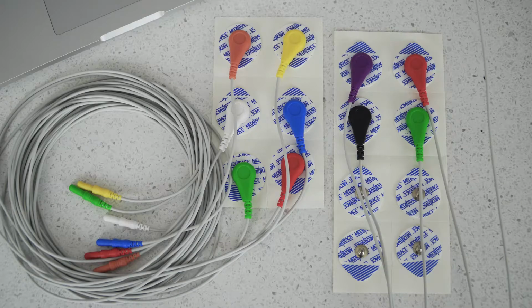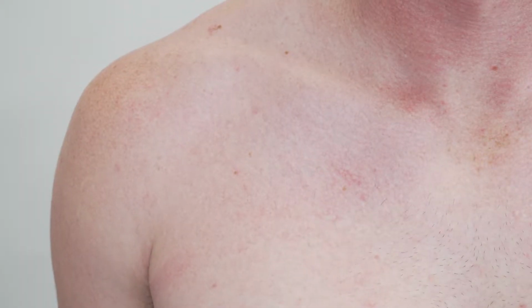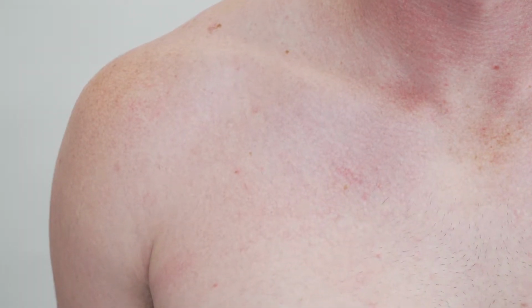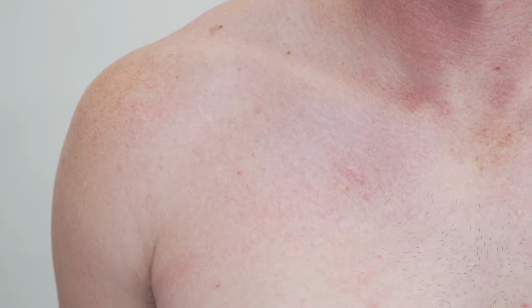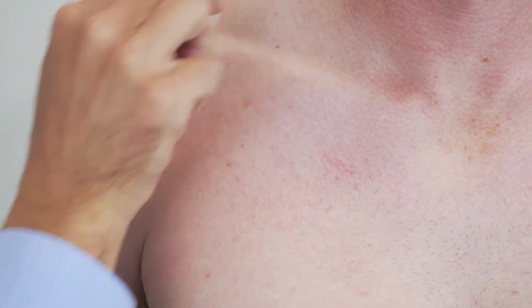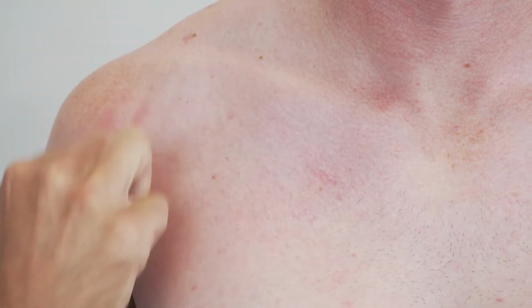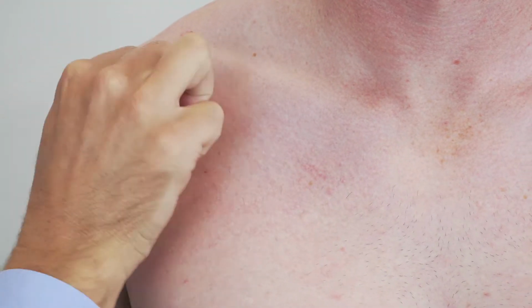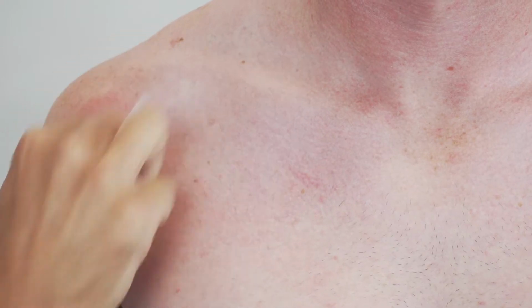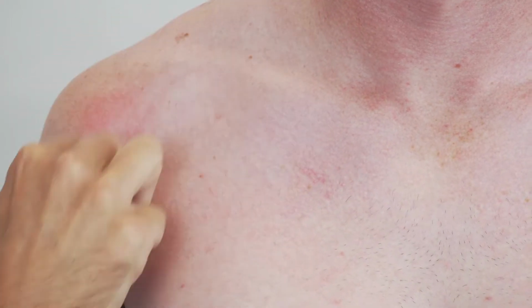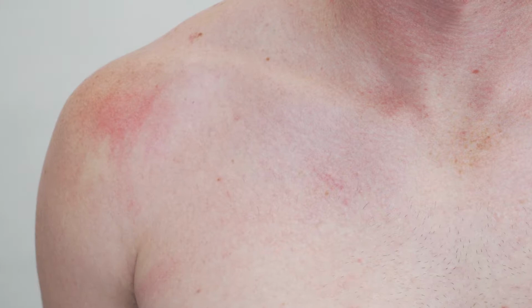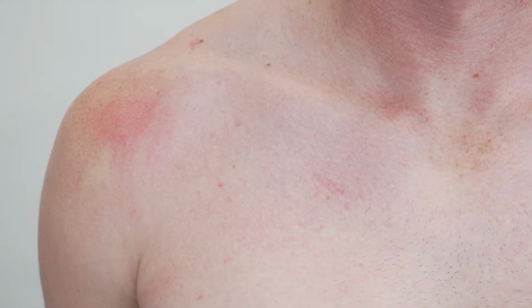Before placing the electrode, it's really important that you prep the skin before you place the electrode. So usually we use these skin cleansing swabs, which are actually just alcohol swabs. And we just wipe down the area, wipe it down really well. This is just to remove any oils which can cause drift in your signal. And now we can place the electrode.